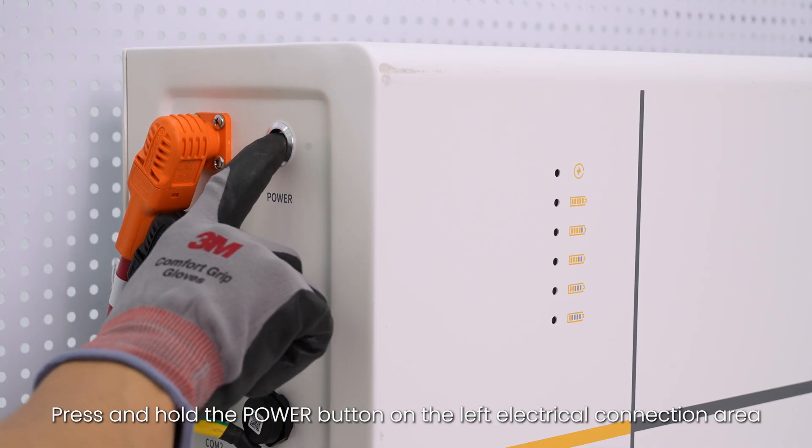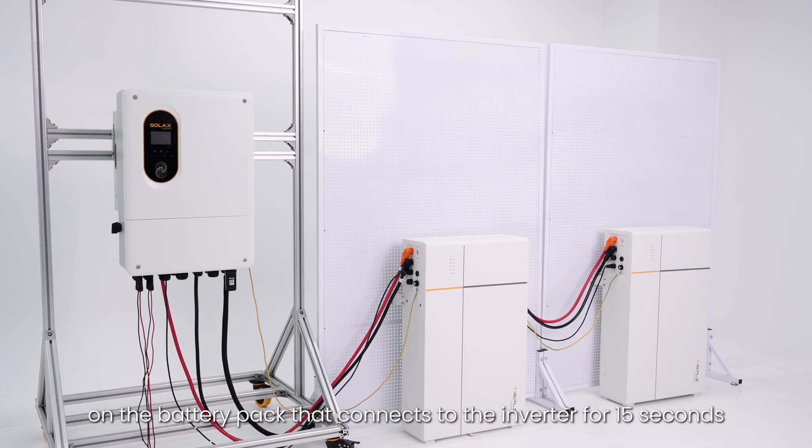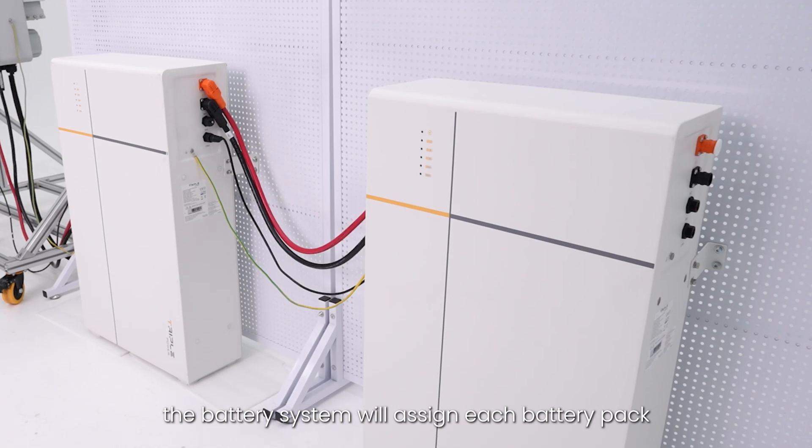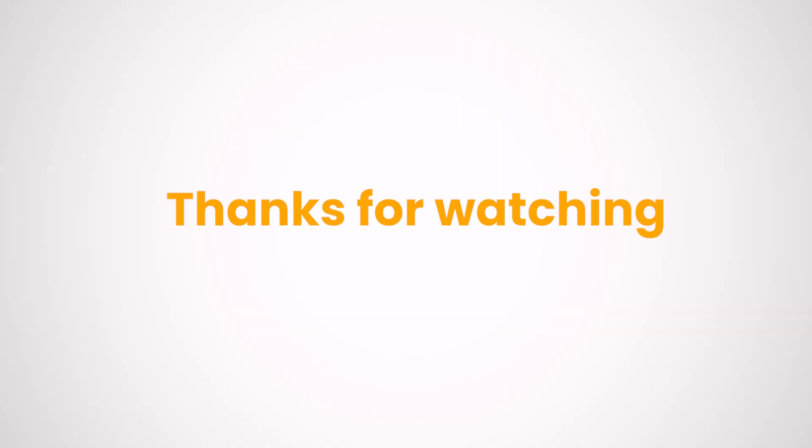Press and hold the power button on the left electrical connection area of the battery pack until the LED lights appear. Regarding the first start, after pressing and holding the power button on the battery pack that connects to the inverter for 15 seconds, the battery system will assign each battery pack in a communication loop a unique address. Thanks for watching.